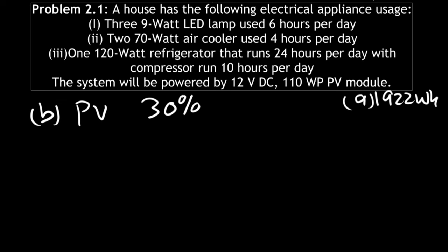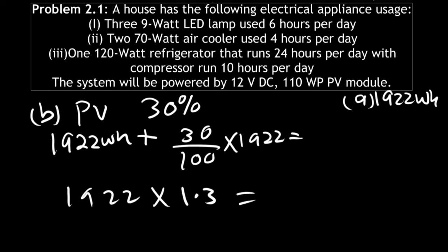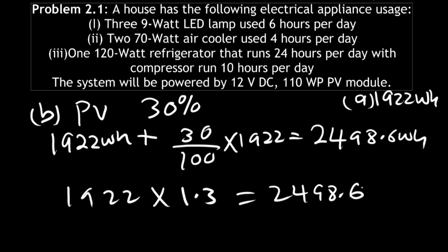So what you do is take our watt hours of 1922 and add 30 percent of that. Alternatively, you can take 1922 directly and multiply it by 1.3. Both approaches give us 2498.6 watt hours. We have now completed the second step, getting 2498.6 watt hours.